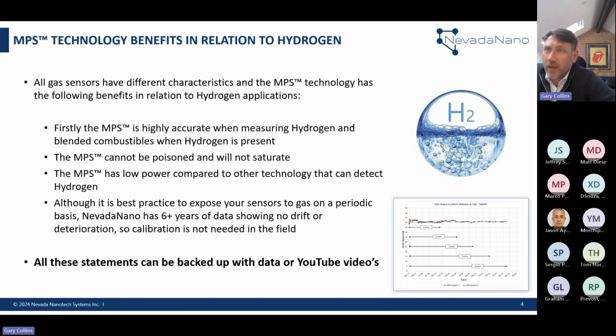So why is the MPS really relevant to hydrogen? Traditional sensors add a lot of value and have done a good job for years, but as the hydrogen economy grows, more so in Europe and Asia and now expanding across the Americas, certain traditional sensors like infrared cannot detect hydrogen, and Pellistors, another traditional sensor, are quite high power and can have problems with saturation or getting poisoned. This means the MPS, as it detects hydrogen very accurately, can measure it as an individual combustible gas or in blends of combustibles.